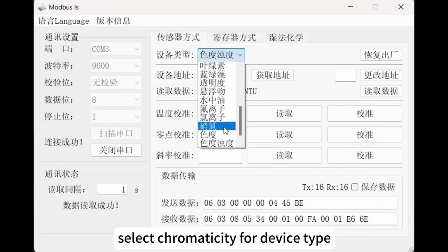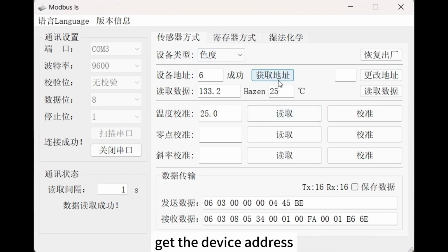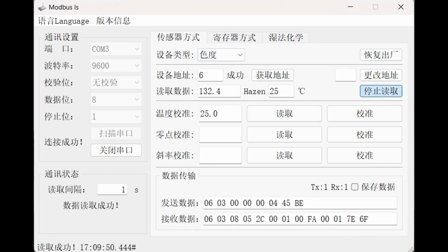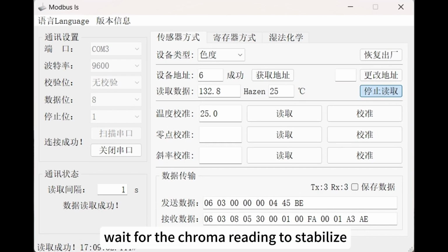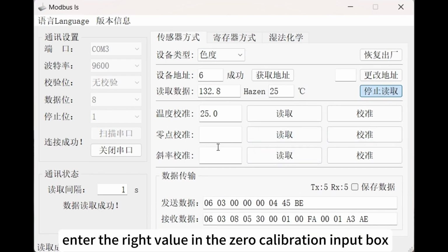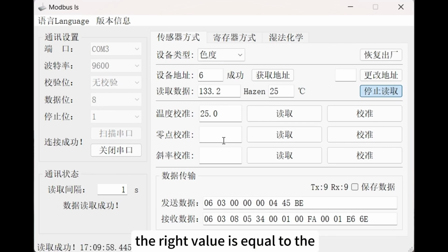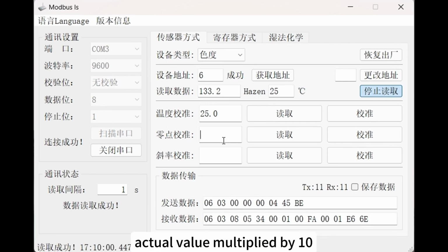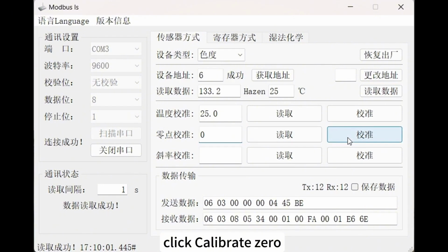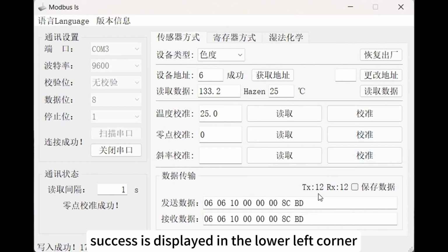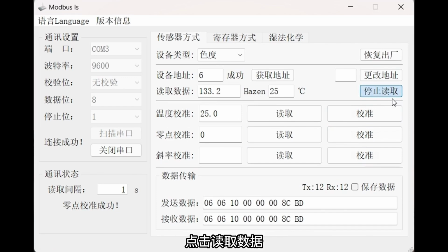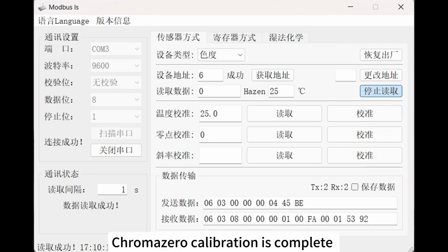Select chromaticity for device type. Get the device address. Click on Read Data. Wait for the chroma reading to stabilize. Enter the right value in the zero calibration input box. The right value is equal to the actual value multiplied by 10. Click Calibrate. Zero calibration success is displayed in the lower left corner. Click Read Data. Chroma zero calibration is complete.